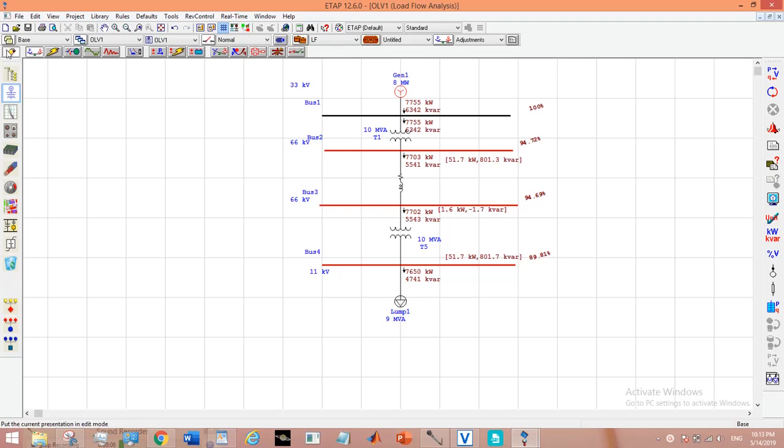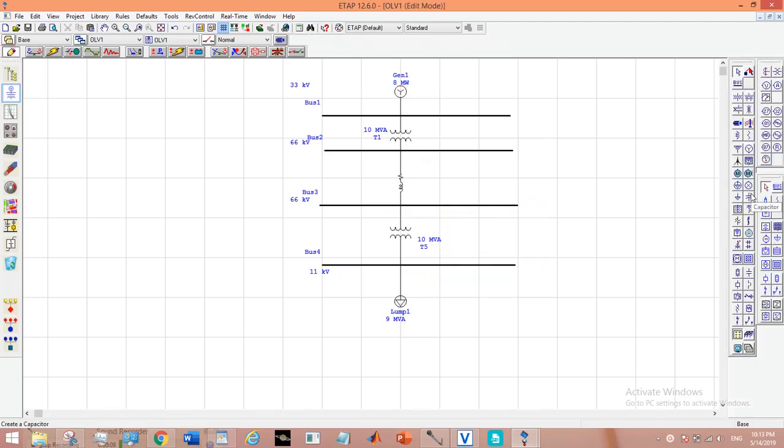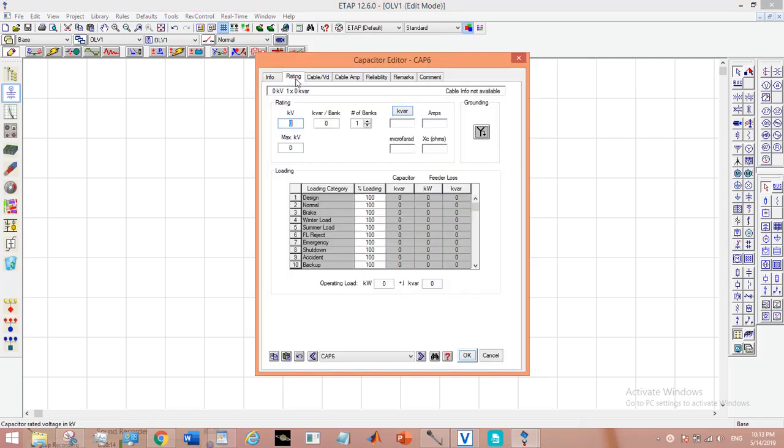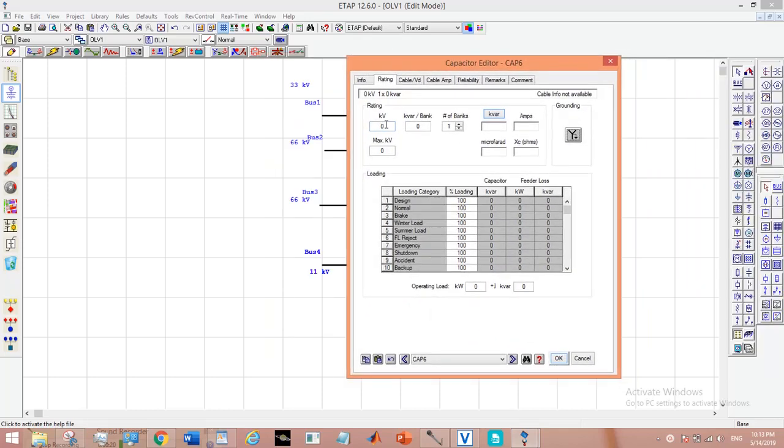Now, let's place the capacitor on bus 4. Its rating, 11 kV and 2246 kVAR. We actually won't find a capacitor bank of this rating. We will have to round off it to a certain value. But in ETAP we can enter this value.